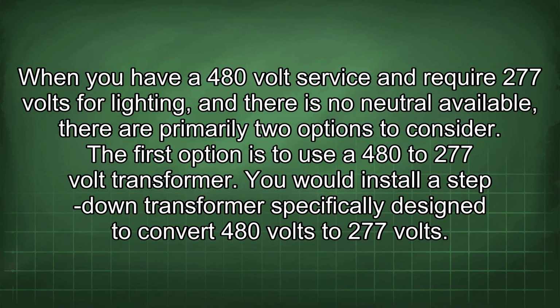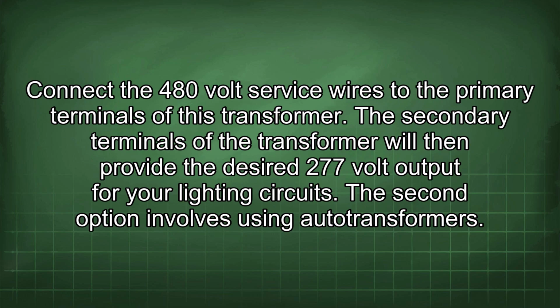When you have a 480 volt service and require 277 volts for lighting, and there is no neutral available, there are primarily two options to consider. The first option is to use a 480 to 277 volt transformer. You would install a step-down transformer specifically designed to convert 480 volts to 277 volts. Connect the 480 volt service wires to the primary terminals of this transformer. The secondary terminals of the transformer will then provide the desired 277 volt output for your lighting circuits.